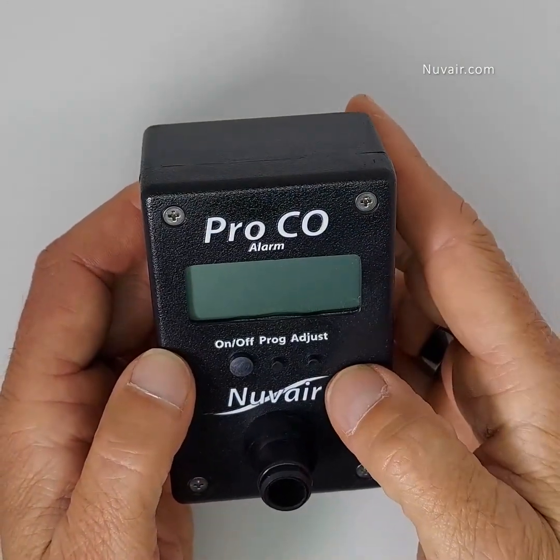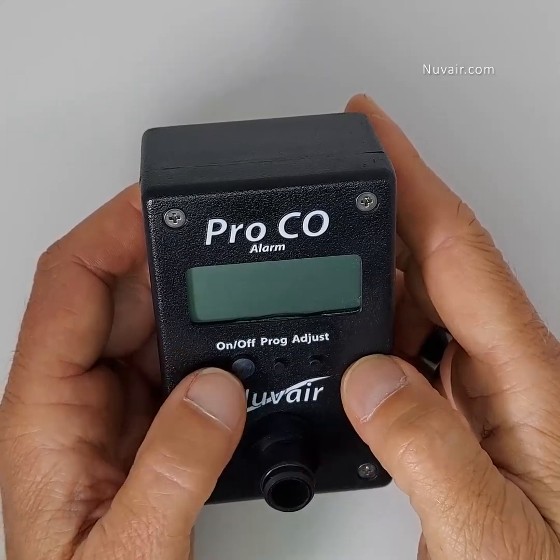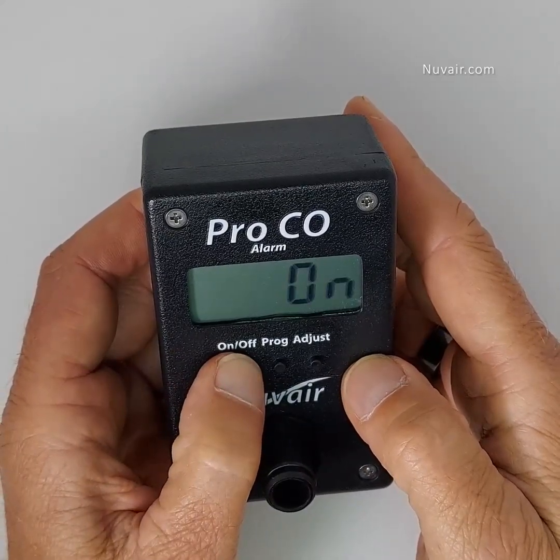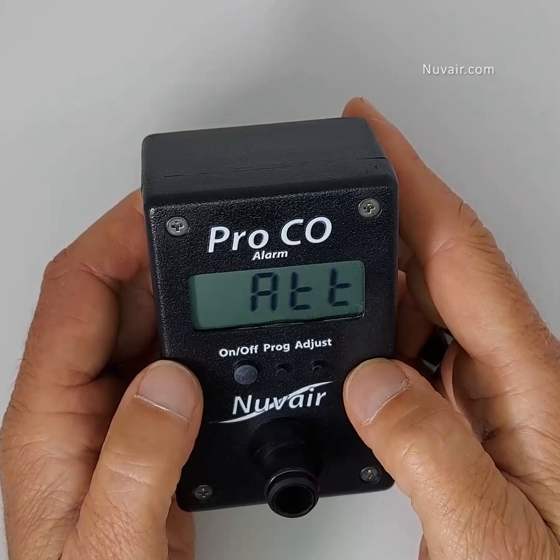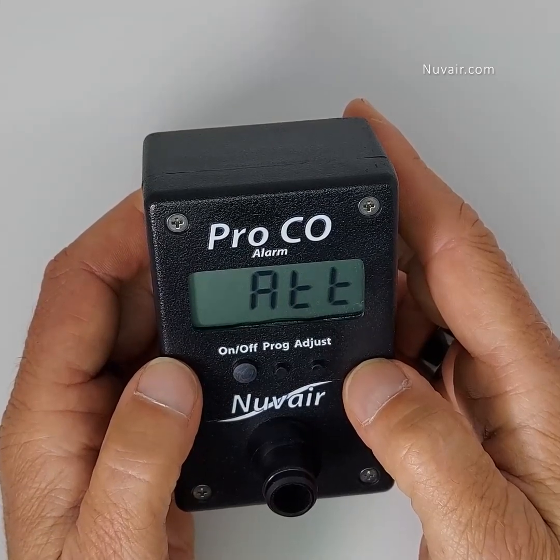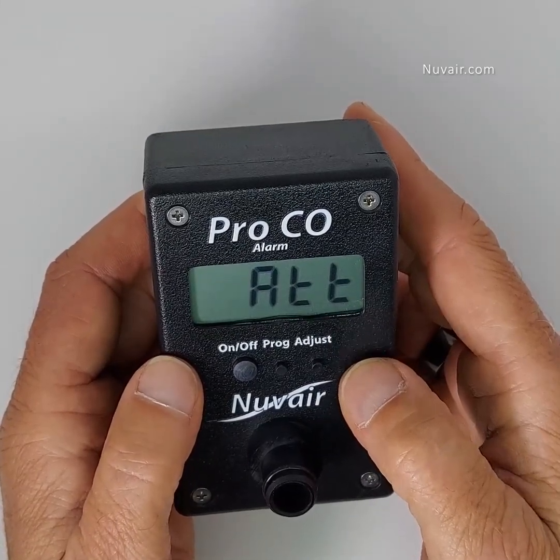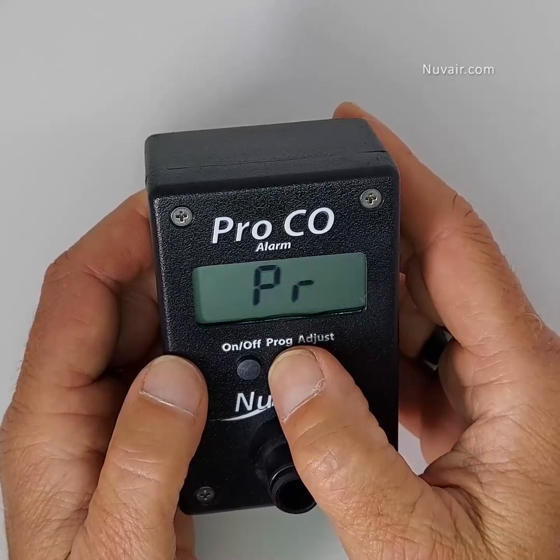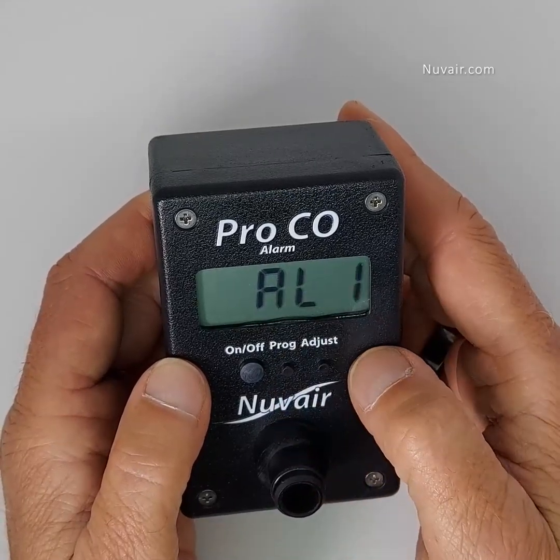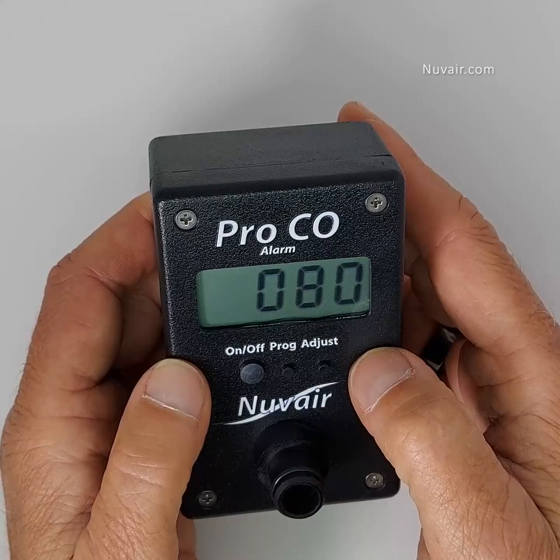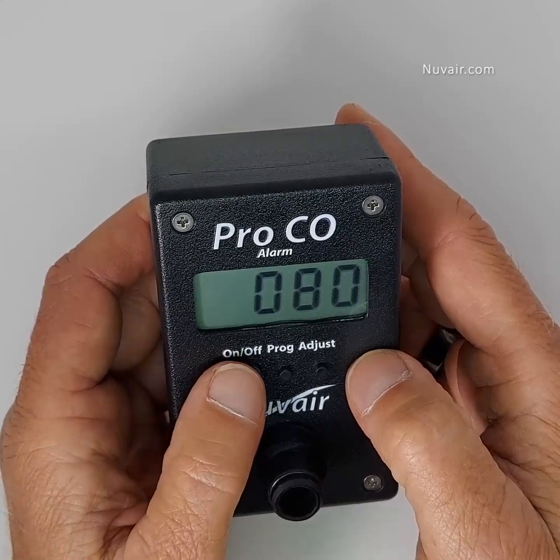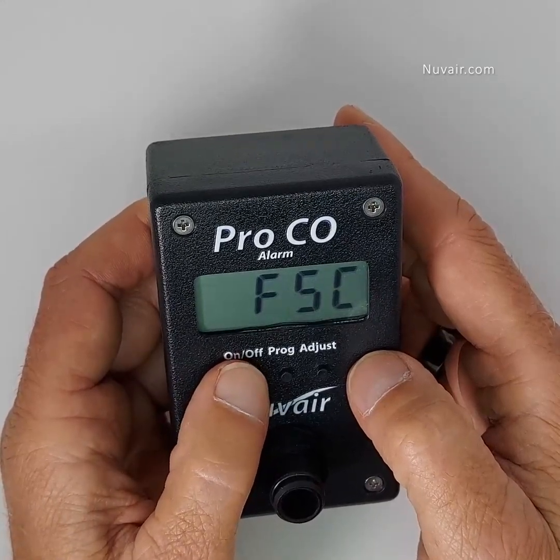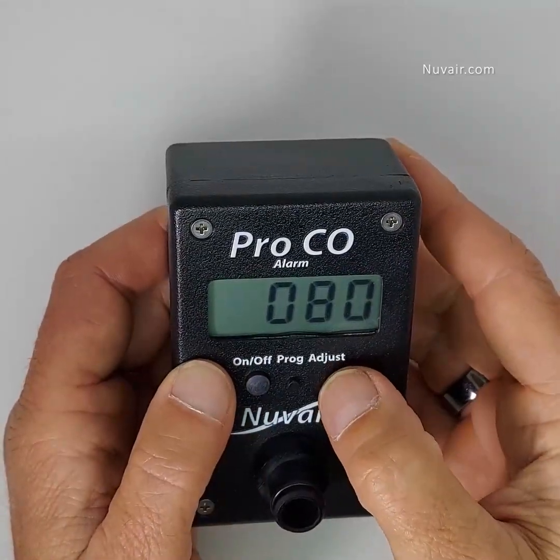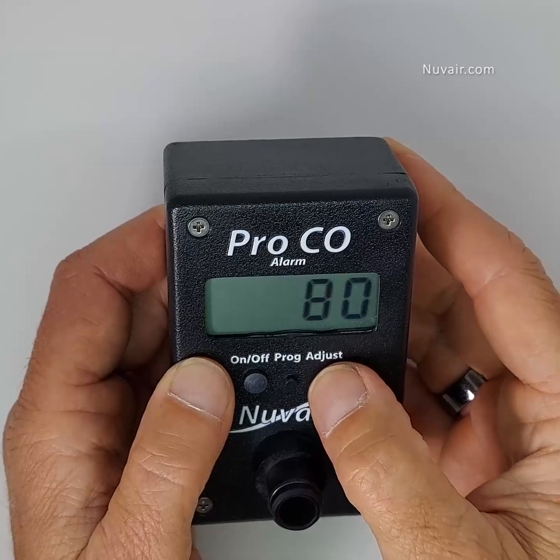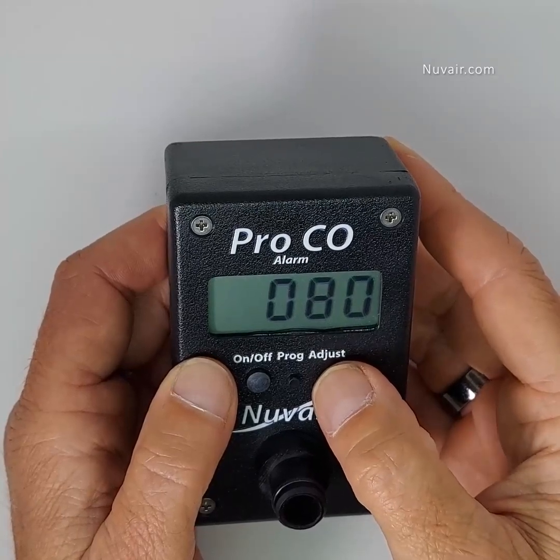Button functions. To switch on, hold the on-off button until the sensor powers up. With the analyzer powered on, and after pressing and holding the PROG, or program button, the letters P and R display on the screen. The on-off button cycles through the programming screens. The adjust button selects which digit to program. The PROG, or program button, changes the value of the blinking digit.